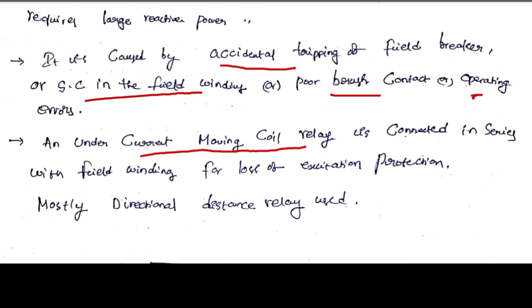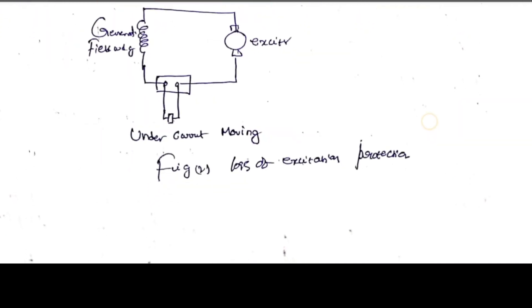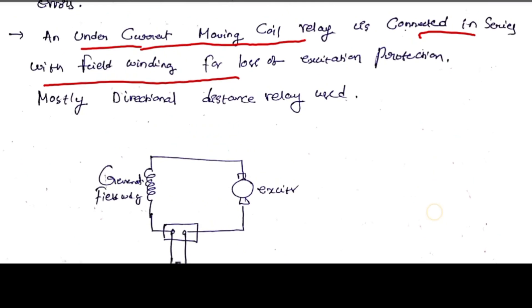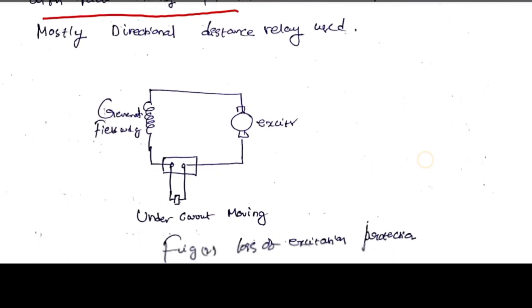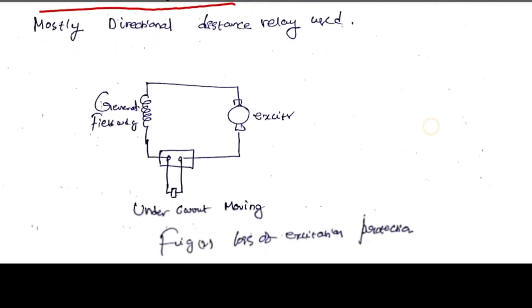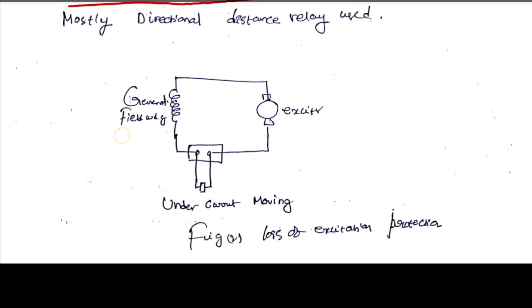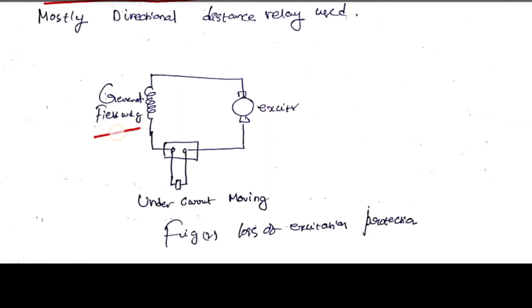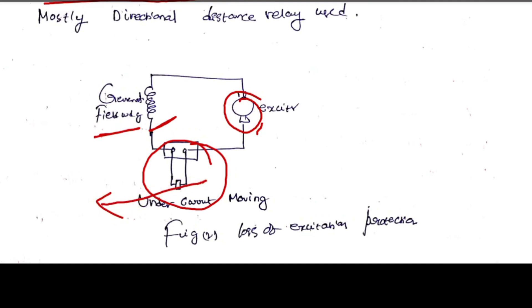An undercurrent moving coil relay is connected in series with the field winding for loss of excitation protection. You can see in this diagram the protection against loss of excitation. Mostly, a directional distance relay is used for field winding protection. In case of alternator failure of excitation between the exciter and field winding, we provide an undercurrent moving coil relay. Whenever the exciter fails, the relay gives a signal to the operator that loss of excitation is happening.